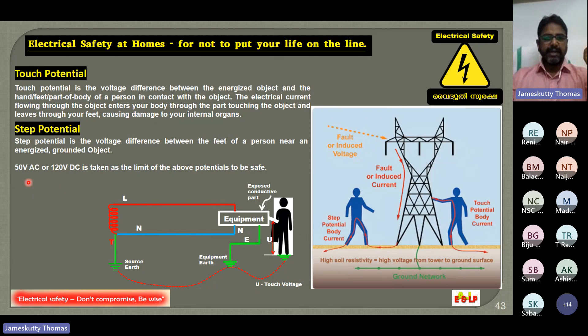So here, touch potential was the cause of the accident. Step potential is the voltage difference between the feet of a person near an energized or grounded object. Both touch potential and step potential have threshold values: the entry point for creating an accident is 50 volts AC or 120 volts DC. So if the step potential or touch potential exceeds 50 volts, it can cause an accident.